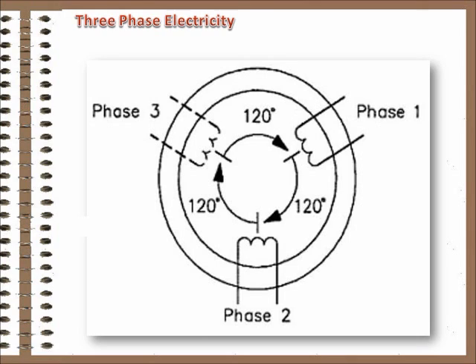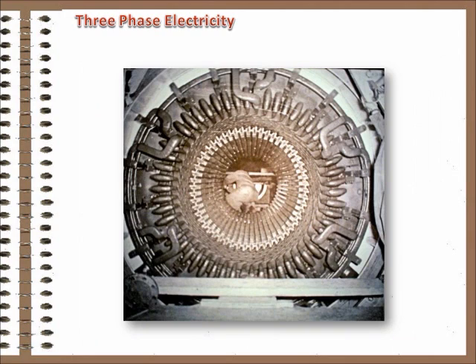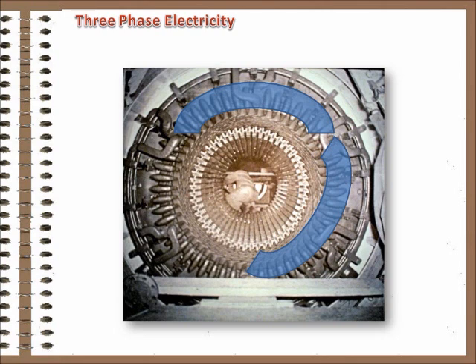But the generators don't have just one continuous wire inside them. There are actually three separate sets of wires inside each generator casing. The wire sets are spaced evenly around the interior of the generator case, or stator as it's called, dividing the 360 degree circle into three 120 degree segments.